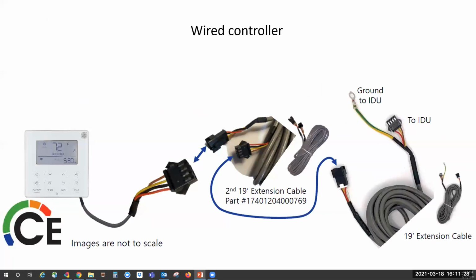Now, once again, we're going to talk compatibility chart for your wired controller. You do not splice these. They just plug right in. They are communicating wires. If you splice them, you're going to have an issue. So you want to order the proper extension cable for however far you are away from your unit.